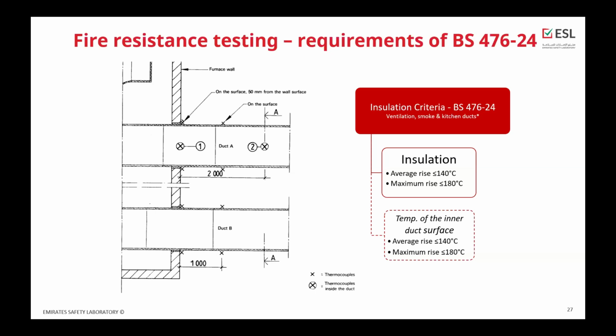However, the average rise criteria is calculated based on the thermocouples which are placed on the normal thickness of the duct. For example, if the first 4 thermocouples are placed on some additional protection of the fire stopping system, only the next 4 thermocouples count to the average. As a laboratory, we have the right to put additional thermocouples if we can identify a hotspot, a risk for the insulation criteria. The air thermocouples, presented as number 1 and number 2, are only for your information or certification information.